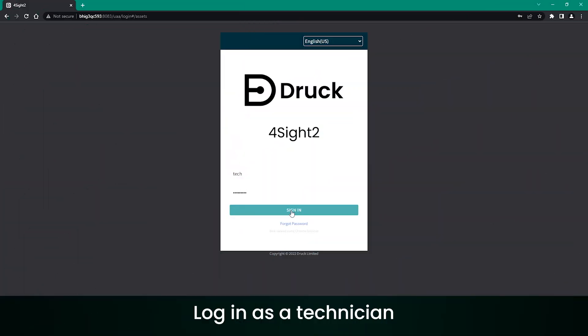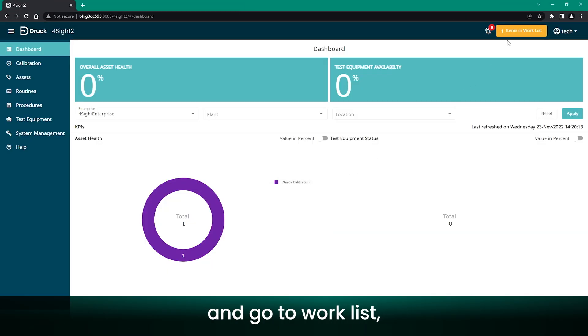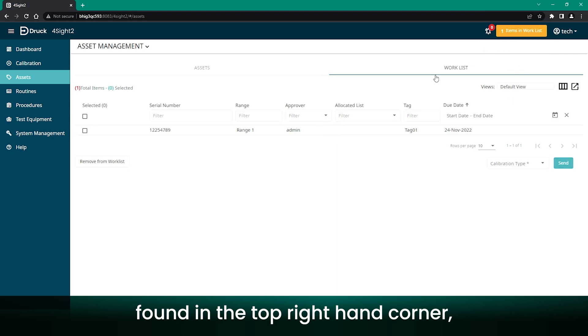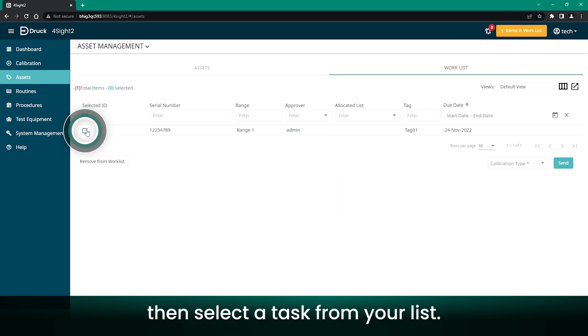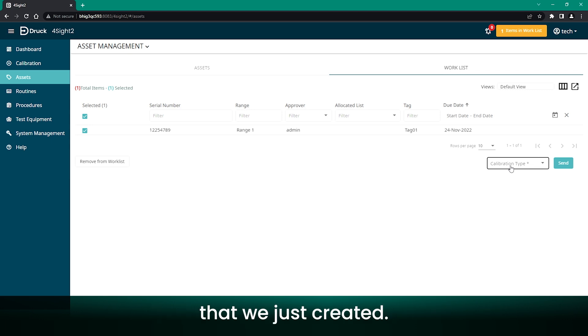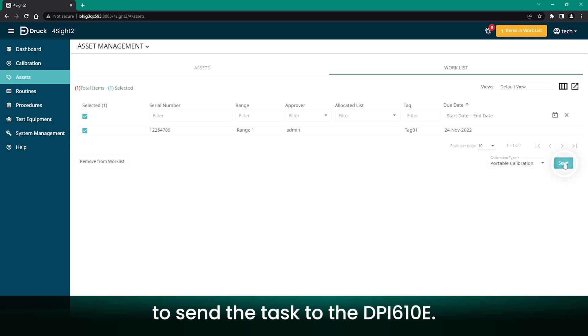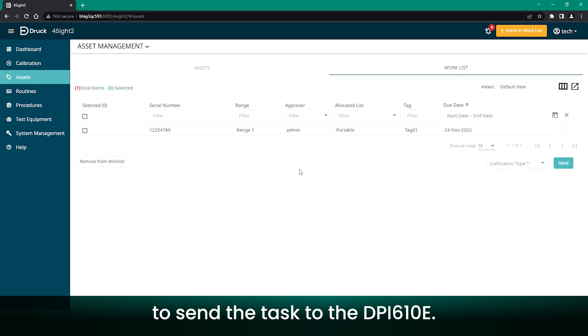Log in as a Technician, and go to Worklist, found in the top right-hand corner. Then, select a task from your list. I am choosing the Unik 5000 sensor that we just created. I will select Portable Calibration option to send the task to the DPI-610E.